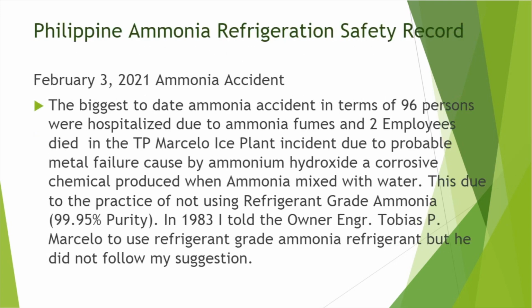On February 3 this year, the biggest ammonia accident to date occurred, in terms of 96 persons hospitalized due to ammonia fumes, and 2 employees died in the TP Marcelo ice plant incident due to the probable metal failure caused by ammonium hydroxide, a corrosive chemical produced when ammonia mixes with water. This is due to the practice of not using refrigerant-grade ammonia. And in 1983, I told the owner, the late engineer Tobias Marcelo, to use refrigerant grade, but he didn't follow my suggestion.